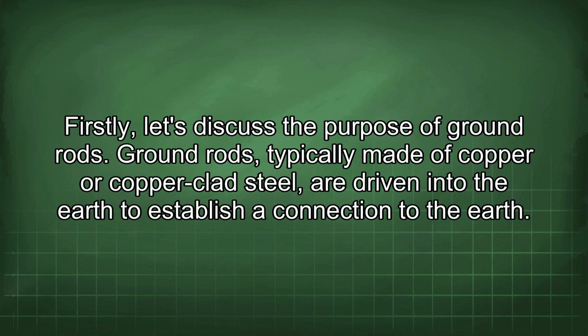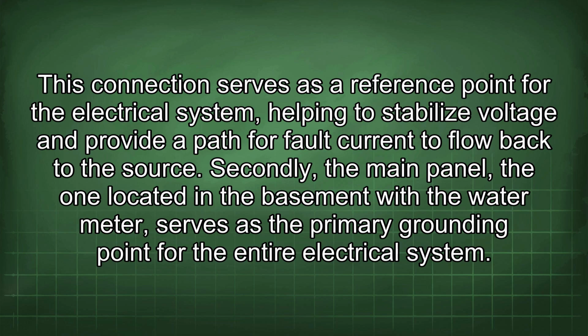Firstly, let's discuss the purpose of ground rods. Ground rods, typically made of copper or copper-clad steel, are driven into the earth to establish a connection to the earth. This connection serves as a reference point for the electrical system, helping to stabilize voltage and provide a path for fault current to flow back to the source.